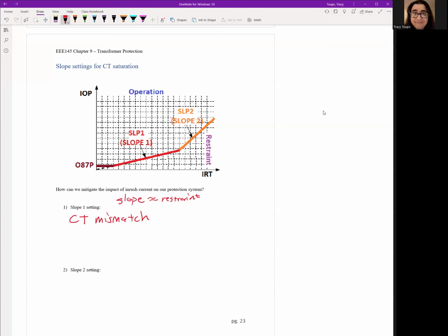Okay, so for example, see here with slope settings for CT mismatch. I think SEL relay says SLP1, that's their setting, is equal to 25%. That's what they suggest for their relays. I think GE and other manufacturers might say restraint 1, restraint 2, right? But we'll go with SEL because that's what most people use. So the first slope is always for CT mismatch, which we covered last class period. Now slope 2, this is more for CT saturation.